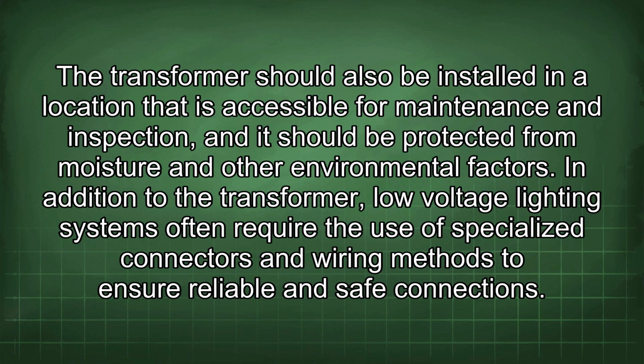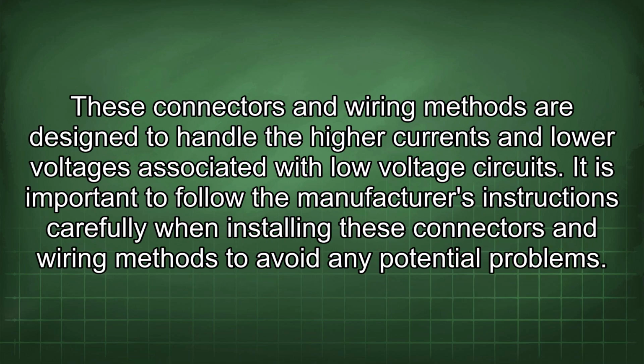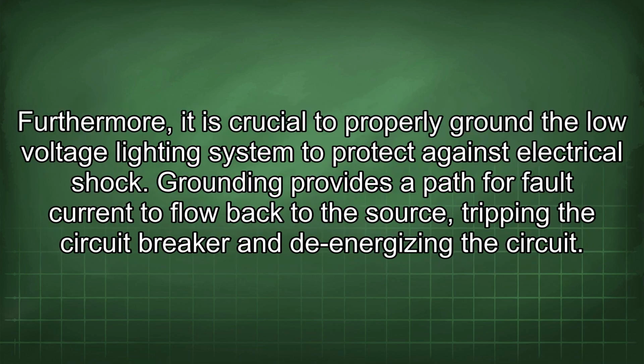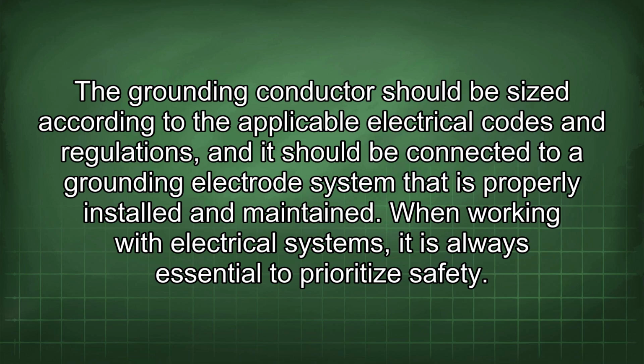In addition to the transformer, low-voltage lighting systems often require the use of specialized connectors and wiring methods to ensure reliable and safe connections. These connectors and wiring methods are designed to handle the higher currents and lower voltages associated with low-voltage circuits. It is important to follow the manufacturer's instructions carefully when installing these connectors and wiring methods to avoid any potential problems. Furthermore, it is crucial to properly ground the low-voltage lighting system to protect against electrical shock. Grounding provides a path for fault current to flow back to the source, tripping the circuit breaker and de-energizing the circuit. The grounding conductor should be sized according to the applicable electrical codes and regulations, and it should be connected to a grounding electrode system that is properly installed and maintained.